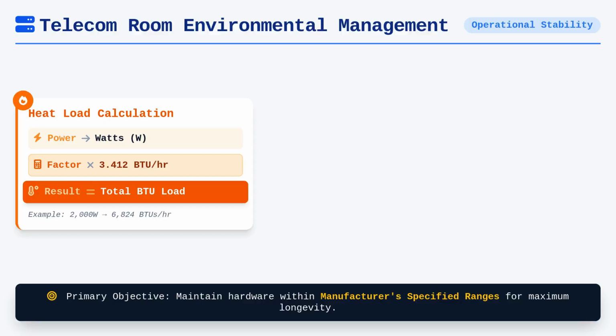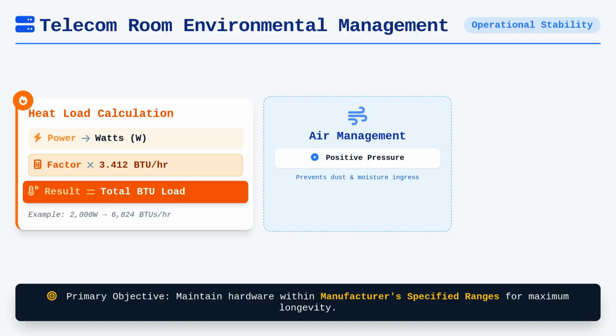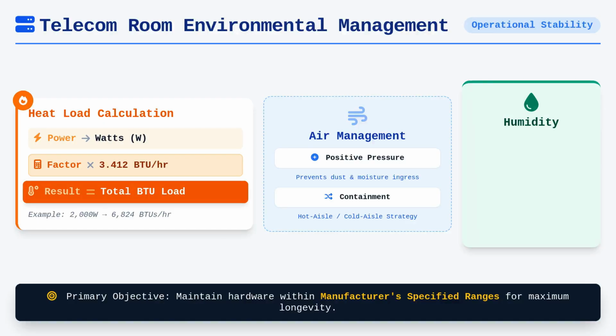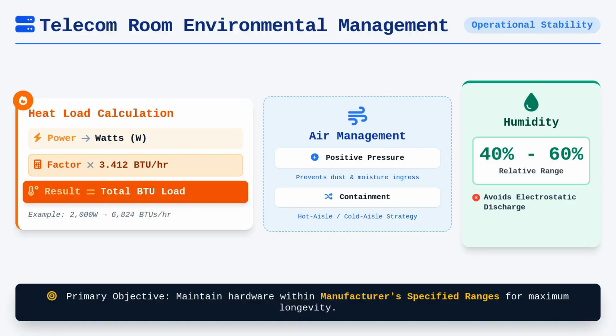However, the calculation is not merely about capacity, but also about the quality of the air being supplied to the space. Maintaining a positive pressure environment is a non-negotiable requirement to prevent the ingress of dust, particulate matter, or moisture that can lead to hardware corrosion. The airflow must be properly managed using hot aisle or cold aisle containment strategies to avoid the mixing of intake and exhaust air, which can otherwise trigger cooling inefficiencies. Relative humidity should generally be maintained within a tight range, typically between 40 and 60%, to mitigate the risks associated with electrostatic discharge or condensation on sensitive circuitry.